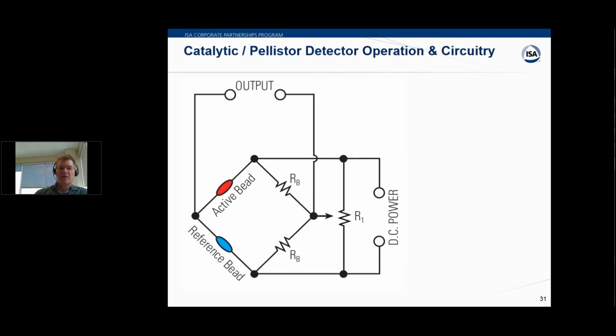And then the catalytic or pellistor. This is the Wheatstone bridge that all of us have probably known since high school. Basically what happens is we have an active bead which has a catalyst on it to encourage the, I'll put in quotes, burning of the gas at a temperature lower than, of course, we would actually get a flame. Though that temperature is still pretty high, around 400 to 600 degrees C. And as we know, any time the temperature changes, we change resistance. And so this changing resistance unbalances the Wheatstone bridge.